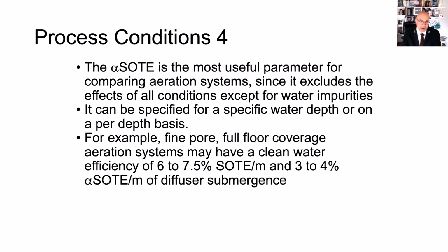So 6 to 7.5% per meter. It's a good number for SOTE in clean water. But when you go to wastewater, it's probably half of that. Okay, so 3 to 4% is a number that we should expect per meter.